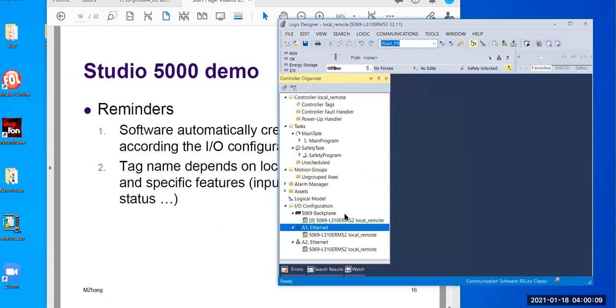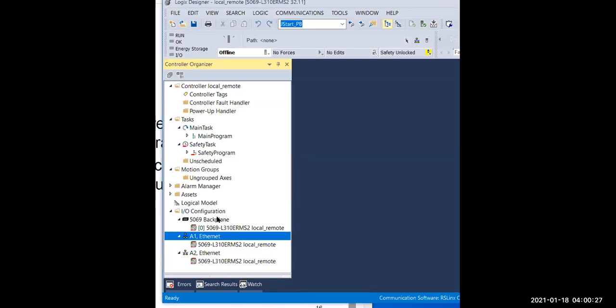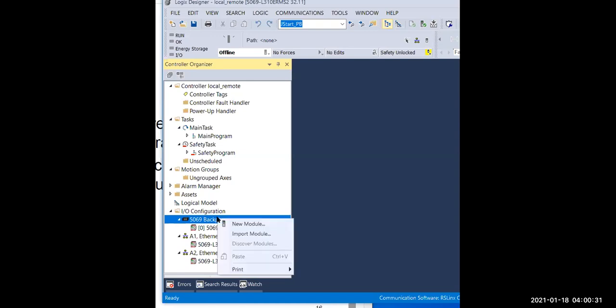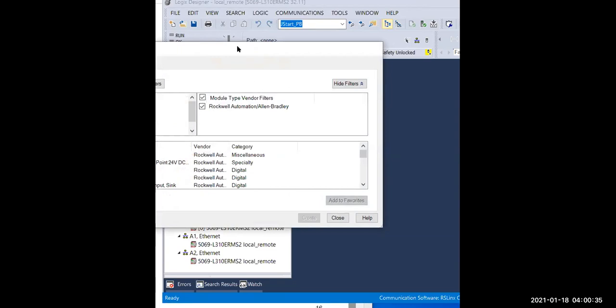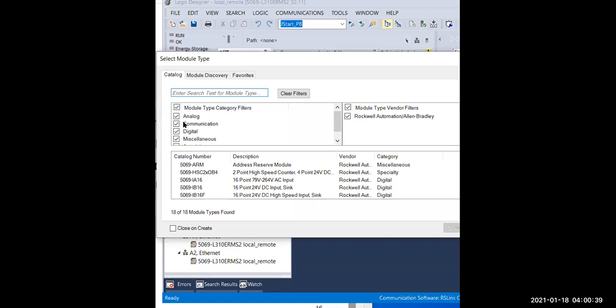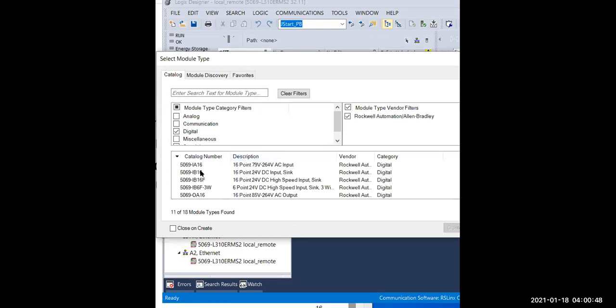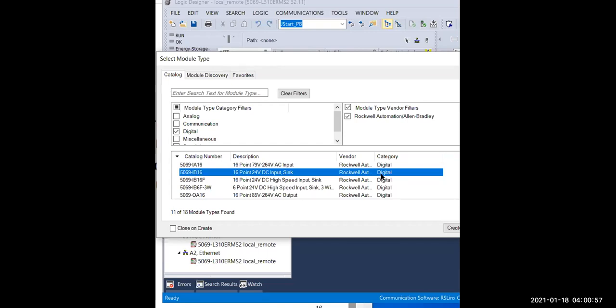Let me go back to the project file. Over here is the I/O configuration. This backplane represents the local chassis. If I right-click and select New Module, I can choose a digital module. Let's select this one — IB16 — which is a 16-channel digital DC input module. I'll just accept the default settings and create it.